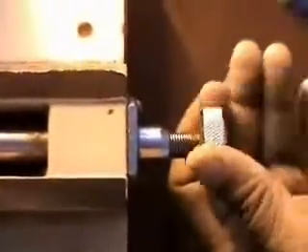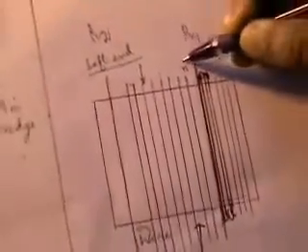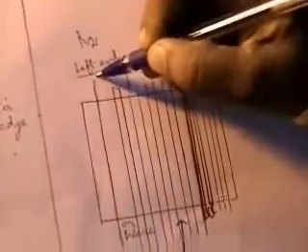This reading will be R2. Do the whole readings in one shot. That is, first edge of contact, then N, then N plus 5, N plus 10, etc., up to N plus 50. Then finally end with R2.